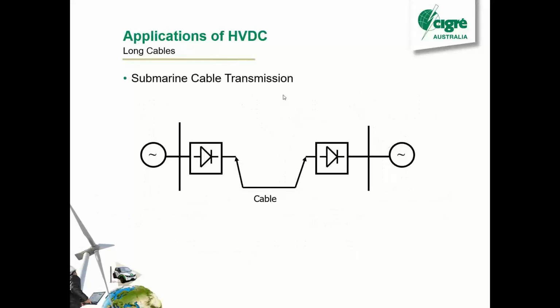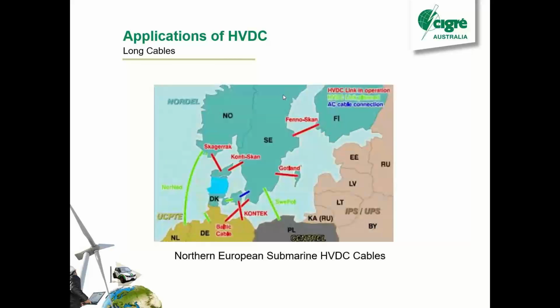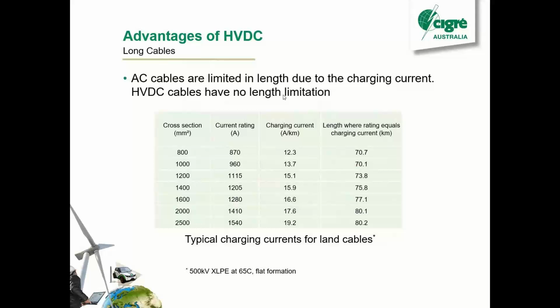The other reason to use HVDC is submarine cable transmission, or actually any cable transmission, to be honest. You can see a few examples of that in Northern Europe. This diagram's a little bit old; there's actually a couple more now. But the main reason for using HVDC for cables is the charging current that you get with AC cables. AC cables are limited in length due to the charging current. Cables have quite a lot of capacitance compared to, say, a transmission line. With an HVDC cable, you've got no length limitation at all. It could be as long as you want.